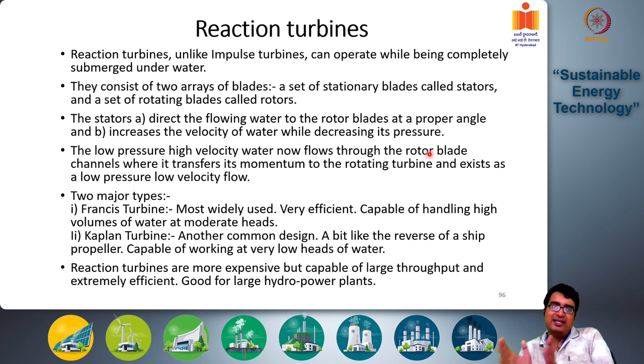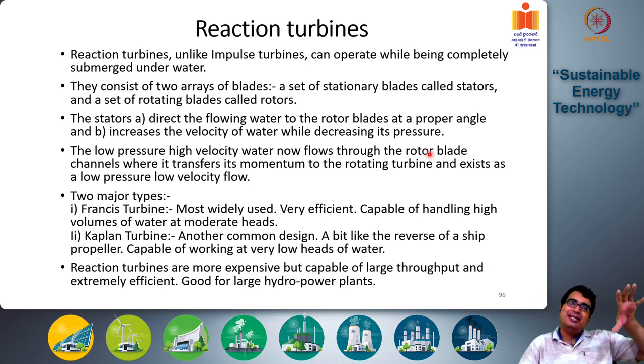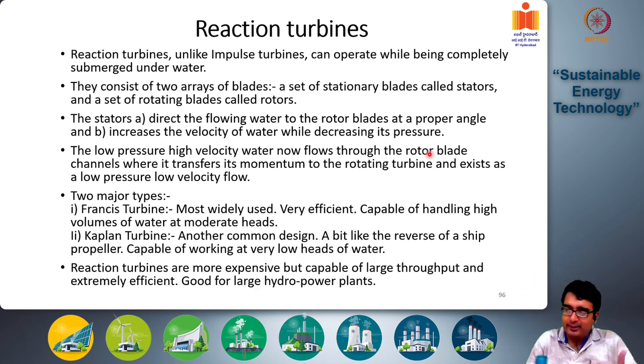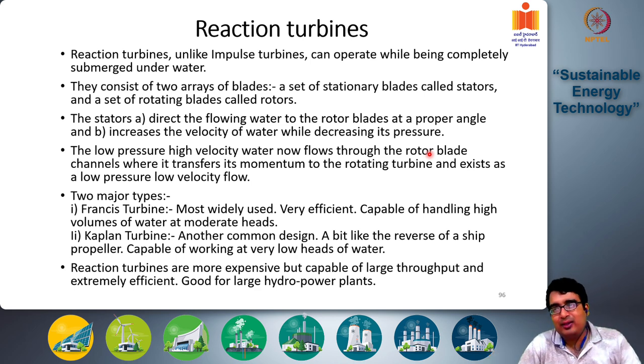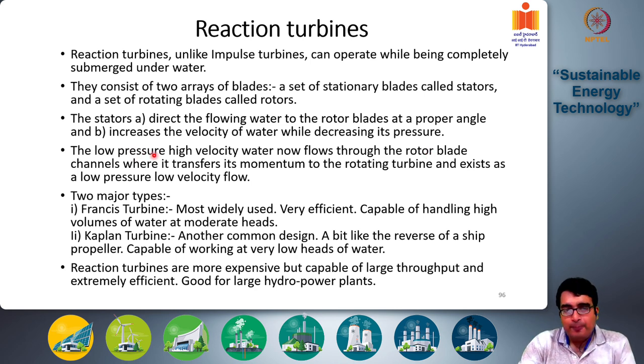The idea is similar to Bernoulli's equation — P/ρ + V²/2 — where we decrease the pressure head and increase the velocity head. The stator blades also direct the water at a proper angle so that maximum energy transfer at the rotor blades happens from the water side to the blade side. The resulting low-pressure, high-velocity water then flows through the rotor blade channels where it transfers its momentum to the rotating turbine.